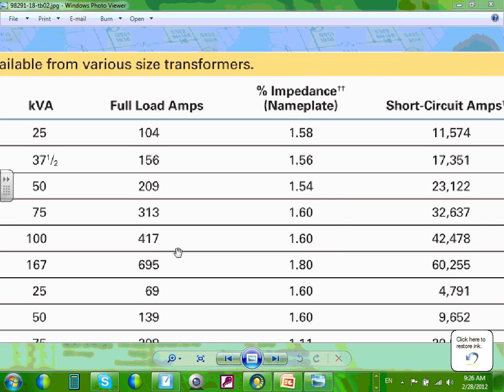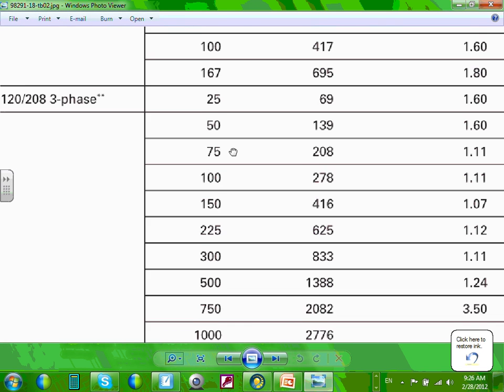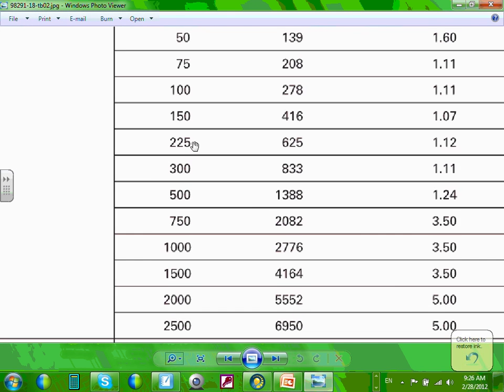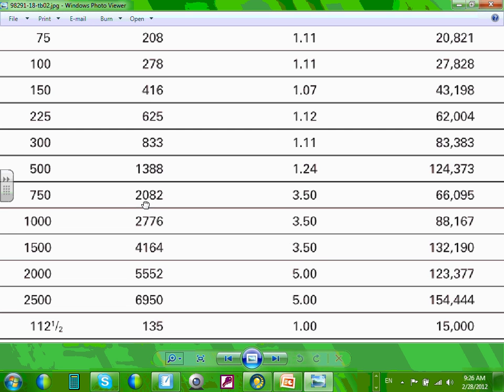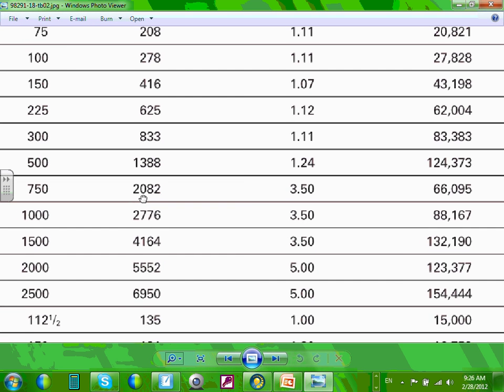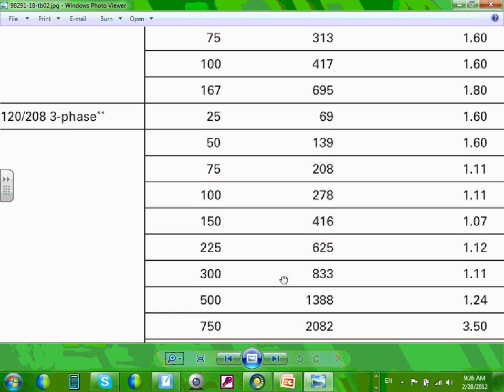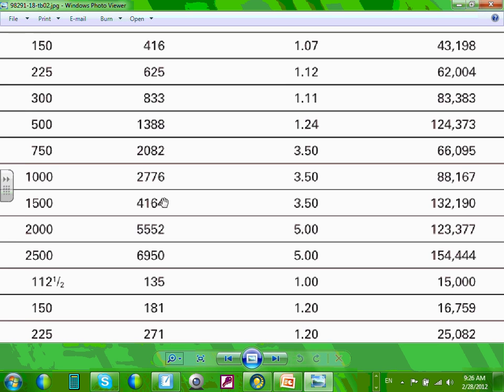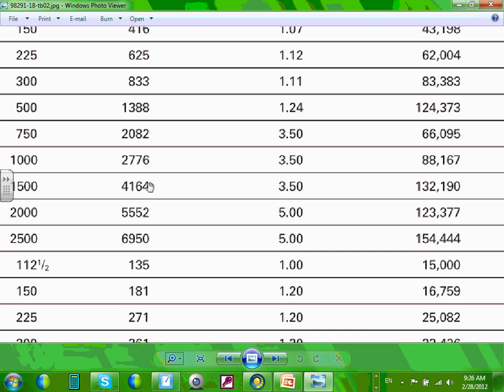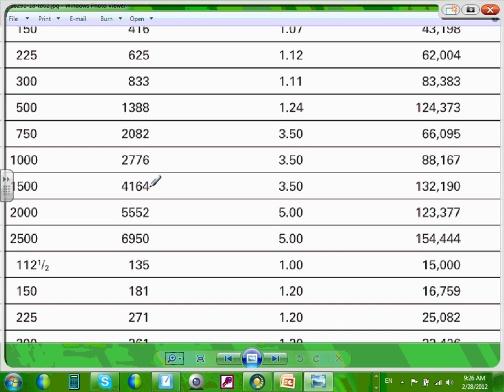So the nice thing about this, guys, since we're doing three-phase, let's go to the three-phase, because this is three-phase 208. Let's just say we have a 500 kVA transformer. What's the voltage? Is this three-phase? Let's say a 500 kVA transformer right here. Okay, so if you look at the 500 kVA transformer right here, the short circuit at the terminal of a 500 kVA transformer is 124,000 amps.